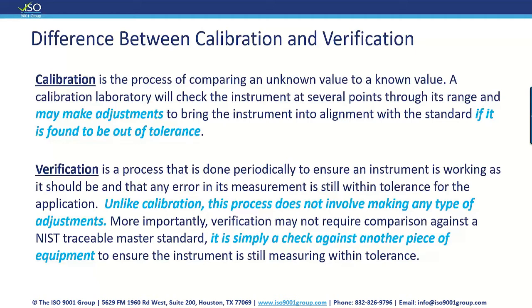So there was no need for you to go to the doctor and get your weight or send your scale out for calibration, because with that 5-pound weight that you know is exactly 5 pounds, when you put it on there, it reads 5 pounds, you've just verified. So that's a really simple example of the difference between calibration and verification.